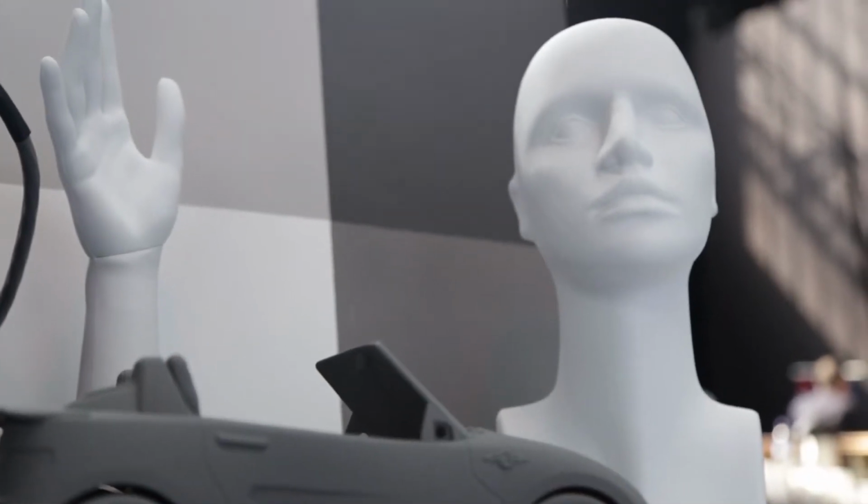So Greg, before we started filming, you said that there was something about your technology that was very close to your heart, very meaningful, that you wanted to talk about specifically. Let's talk about that now. Right, that's our uniform source for the wide-angle field of view. What's really nice about this system is, yes, it can match almost any spectrum that you put in there, and it allows the user to do that. But what's really unique to this one is it can do up to a 220-degree field of view. So you can put a fisheye lens camera in there and flat field over 200 degrees.